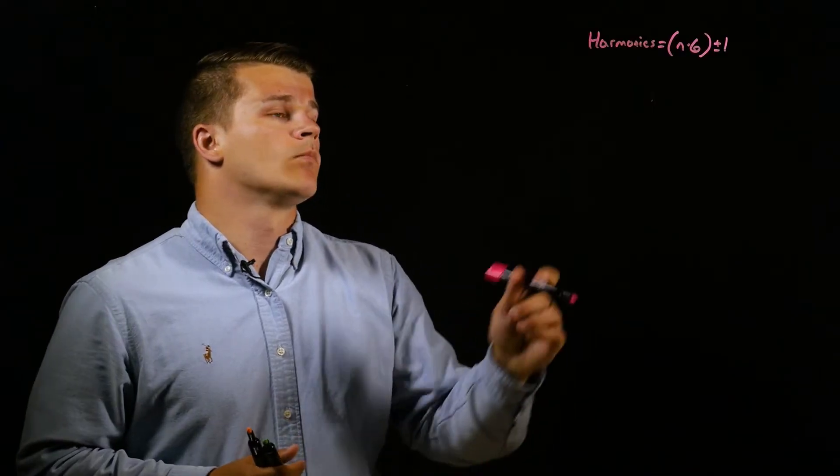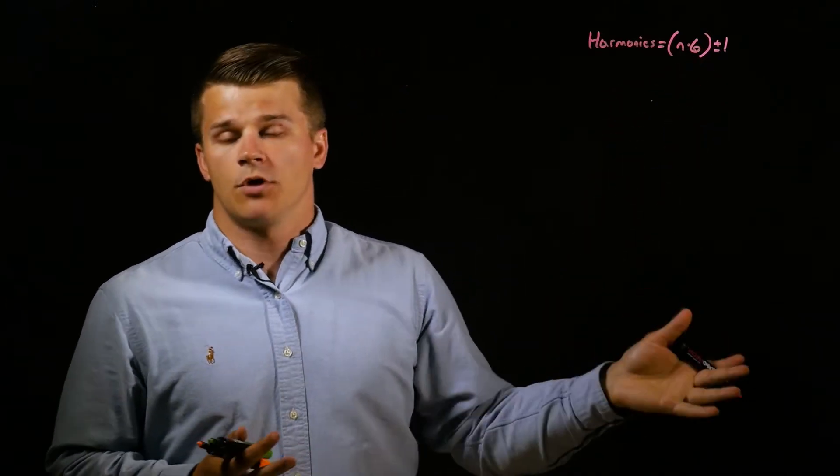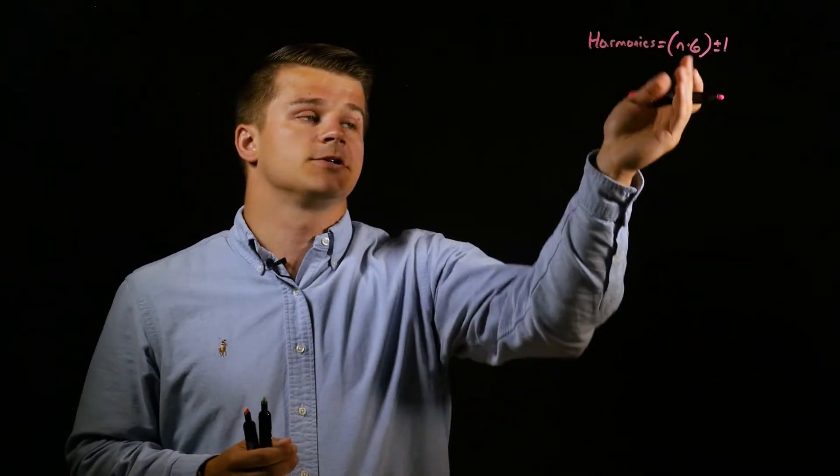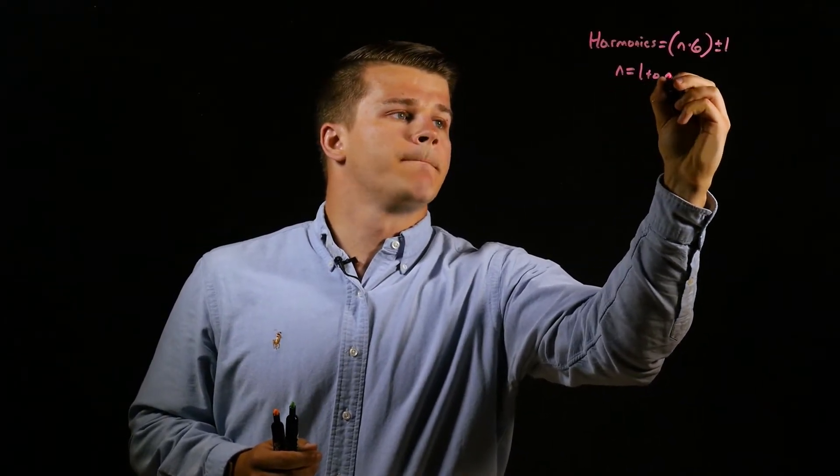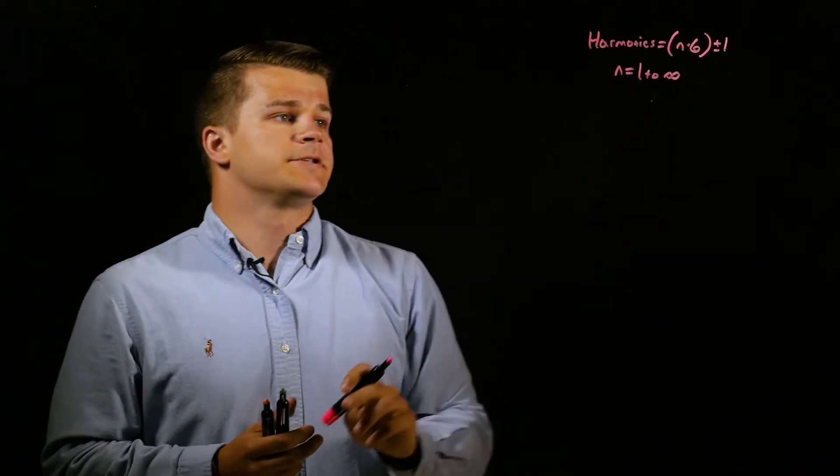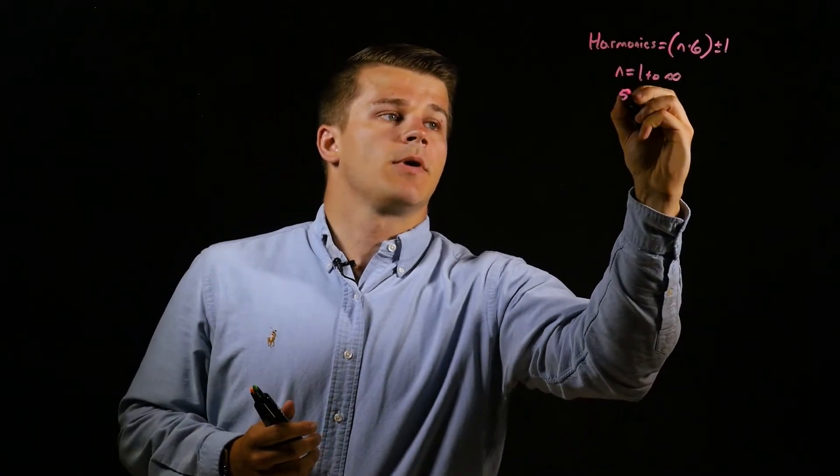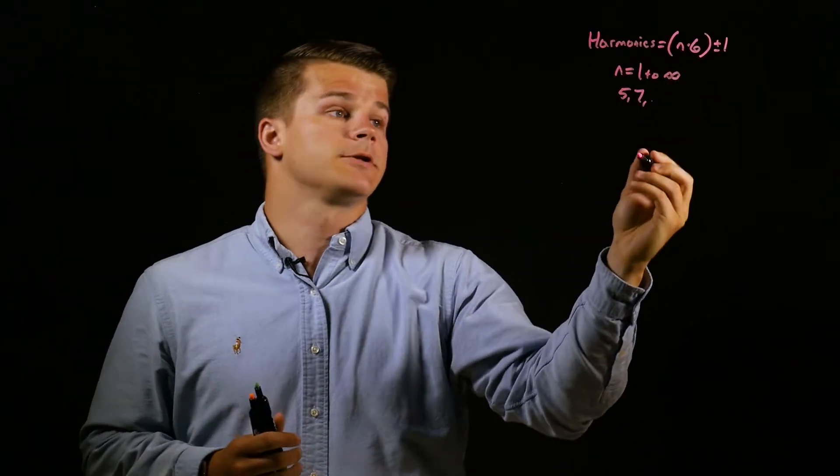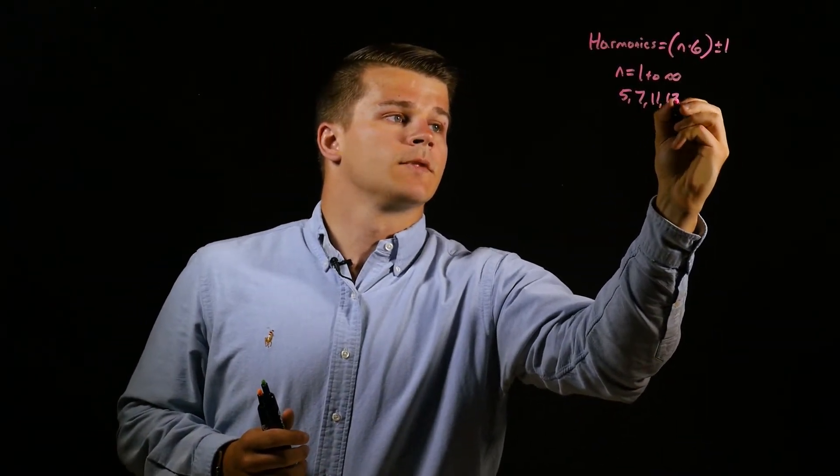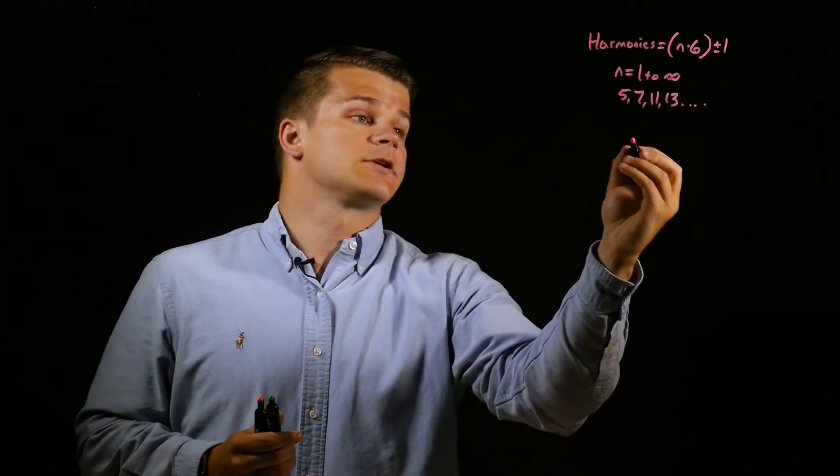Harmonics are integer multipliers of the fundamental frequency. Because our drive is a 6-pulse VFD, we would have a 6 here in this equation. But if you have a 12-pulse VFD, for example, you would replace this with a 12. And then n equals 1 to infinity. So for example, when n equals 1, we get 1 times 6 equals 6 plus or minus 1, so we get harmonics of 5 and 7. If n equals 2, we get 2 times 6 is 12, plus or minus 1 is 11 or 13. And this goes on and on. So these would be the harmonics in a KEB 6-pulse VFD.